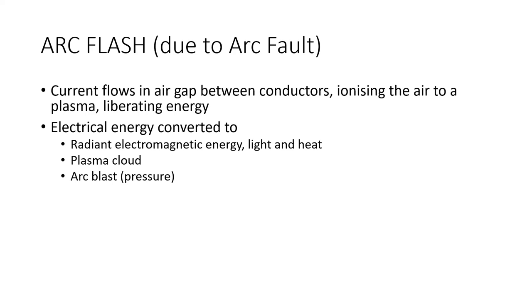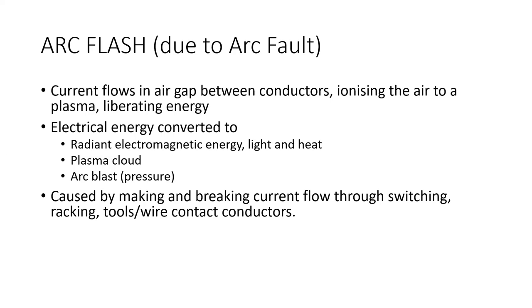There'll be a plasma cloud associated with that arc flash that you'll find later does most of the damage, or is considered to be one of the most important and hazardous features of the arc flash. And there's also an arc blast, a pressure blast. Causes of arc flash can be making and breaking current flow and switching, racking, and often it's tools, wires, and conductive items contacting conductors, usually bus bar in a switchboard.